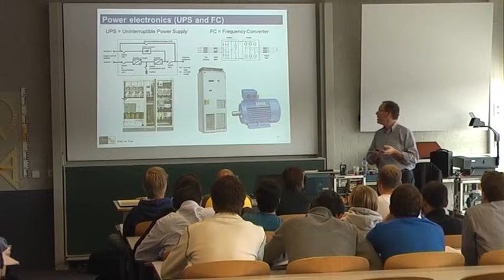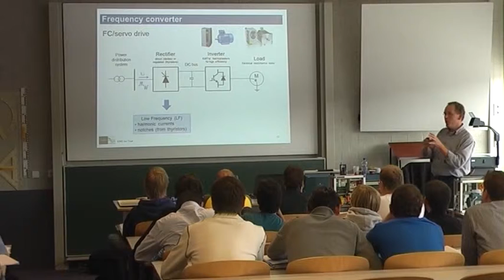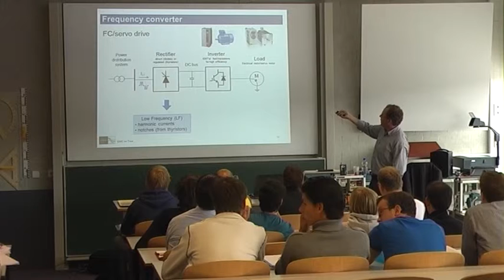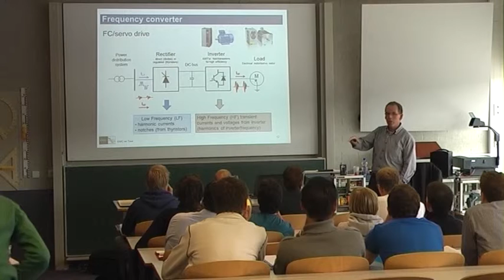Actually what's happening here is the square wave thing that Fritz has showed you. You've got all square waves there and all the coupling effects. And what I want to show you is the capacitive effect here in the motor. So we've got the rectifier here, you've got some harmonics, but that's not your problem, I think. We've got the capacitance here, between the winding and the motor casing. I've got an industrial motor here. There's a winding inside, and it actually sees the capacitance to the aluminium casing, which is earthed with this earth wire. So we've got the square wave thing here, and then the capacitance, and then actually there's a return circuit here. So we get the same type of disturbance currents that Fritz has shown you with the square wave generator.